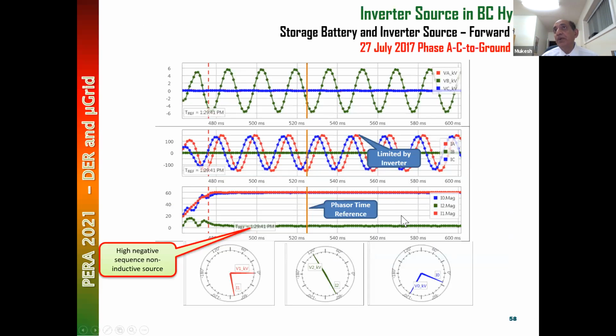In spite of that, it is in a grid follower mode. It supplies a very small amount of negative sequence current. And this negative sequence current is not inductive. This is a very resistive negative sequence current. The point I'm trying to make is that a negative sequence directional element relies on an inductive phase angle relationship, where the negative sequence current leads the negative sequence voltage by 90 degrees. Here it leads by 180 degrees.